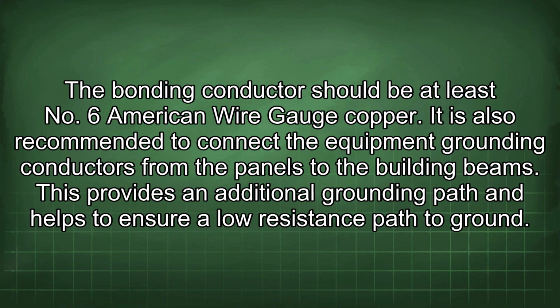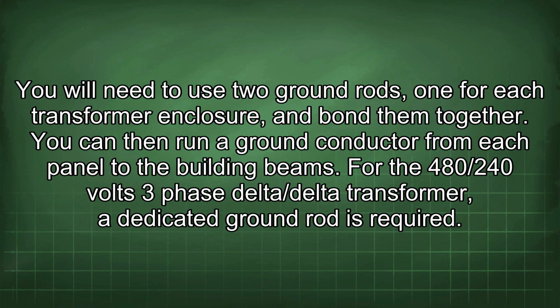It is also recommended to connect the equipment grounding conductors from the panels to the building beams. This provides an additional grounding path and helps to ensure a low resistance path to ground. You will need to use 2 ground rods, one for each transformer enclosure, and bond them together. You can then run a ground conductor from each panel to the building beams.